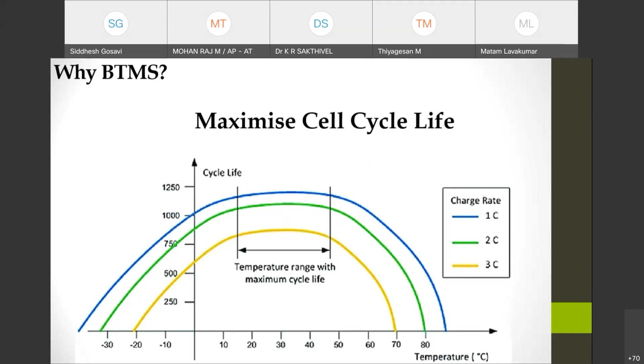Apart from cell cycle life, another major advantage of using the BTMS system is to ensure safety - this addresses the critical thermal runaway issue. There are many root causes for why thermal runaway is caused, and one of the main common reasons is the internal short circuit: say the separator layer gets punctured and the cell is internally shorted.